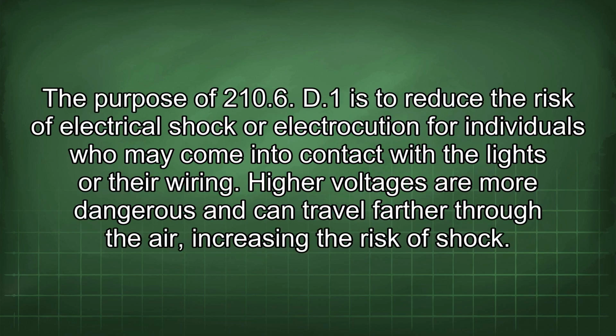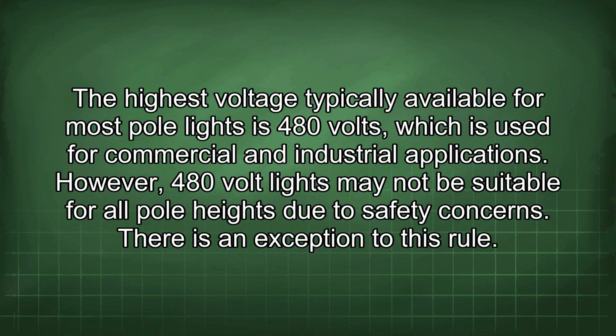The purpose of 210.6(D)(1) is to reduce the risk of electrical shock or electrocution for individuals who may come into contact with the lights or their wiring. Higher voltages are more dangerous and can travel farther through the air, increasing the risk of shock. The highest voltage typically available for most pole lights is 480 volts, which is used for commercial and industrial applications. However, 480-volt lights may not be suitable for all pole heights due to safety concerns.